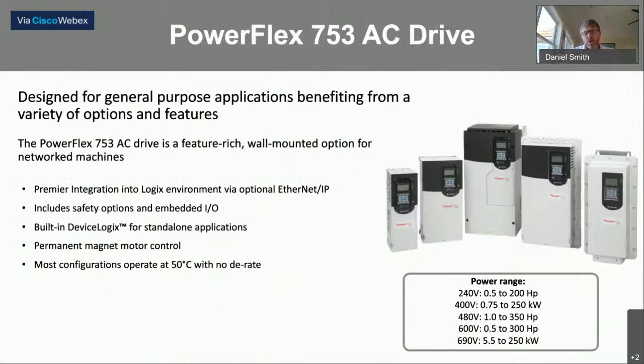So our entry level architectural class drive is the PowerFlex 753. It is available from 1 horsepower all the way to, this slide is actually wrong. It goes to 400 horsepower now, not 350, which is a 477 amp drive. It comes with a little bit of I/O. It has 2 digital inputs, 1 digital output, 1 analog in and 1 analog out on the main control board. There are also 3 additional ports embedded in this drive where you can add more I/O or safety cards or communications cards. So if you wanted to put this drive on Ethernet, it has a native Ethernet card that allows you to integrate it with the ControlLogix platform seamlessly.